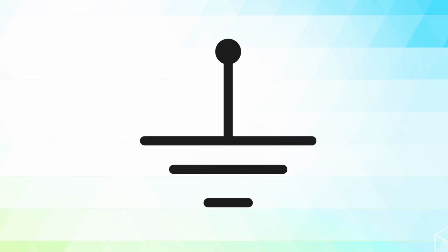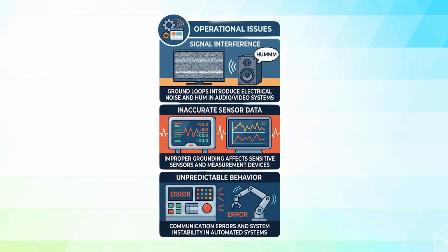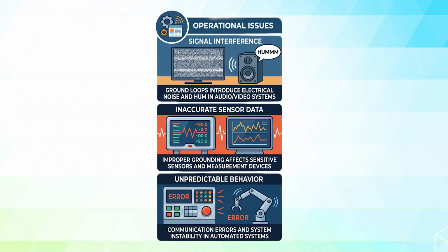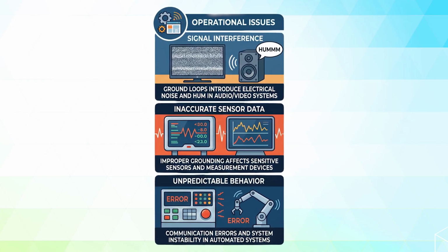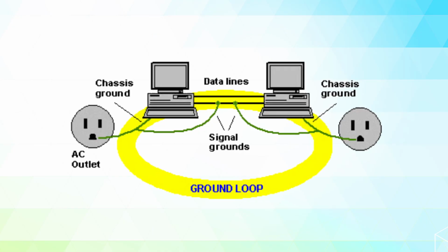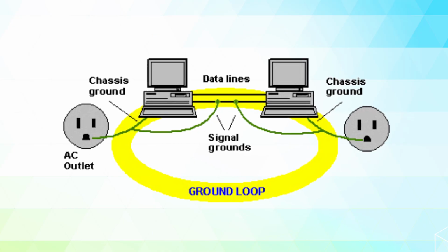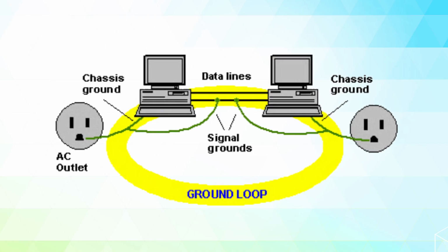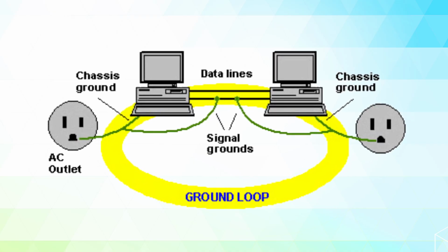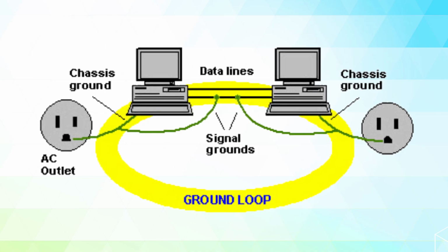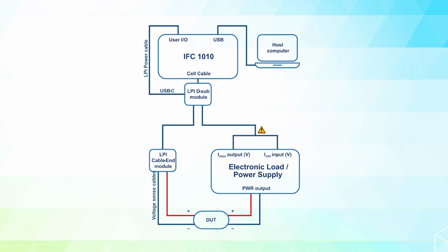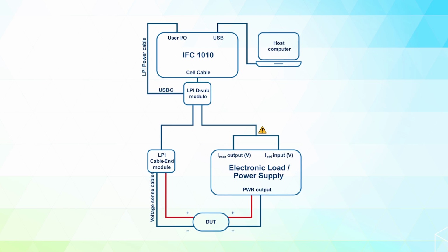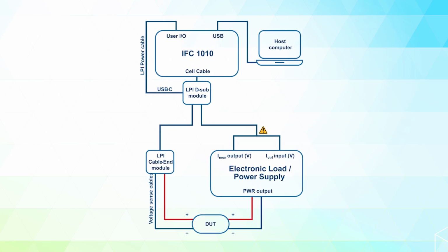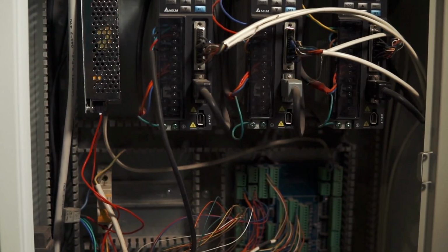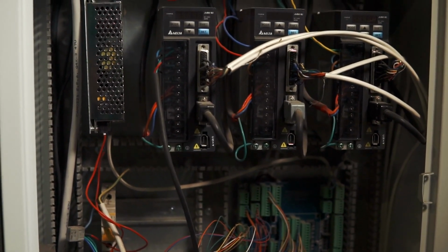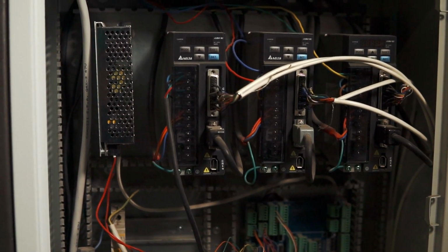Grounding can also make or break a measurement. Improper grounding can introduce offsets, instability, and unwanted noise. One common issue is a ground loop, which happens when two points that should be at the same electrical potential actually have a small voltage difference between them. That unwanted voltage can show up in your measurement, making the signal appear noisy or inaccurate. Using differential inputs, proper shielding, isolated modules, and thoughtful cable routing can help reduce these problems. In many real-world systems, wiring and grounding practices are just as important as the hardware specifications.